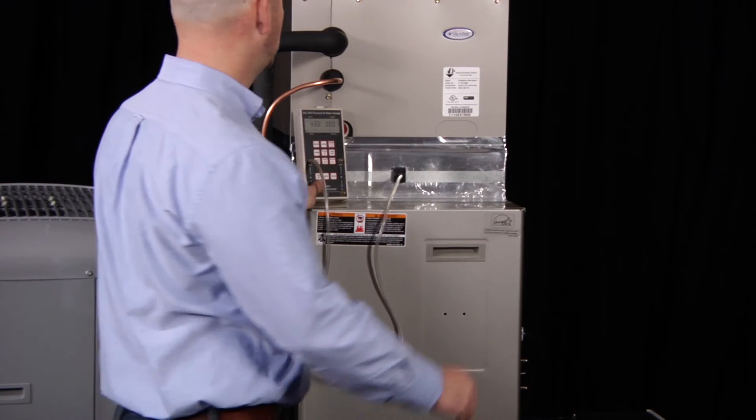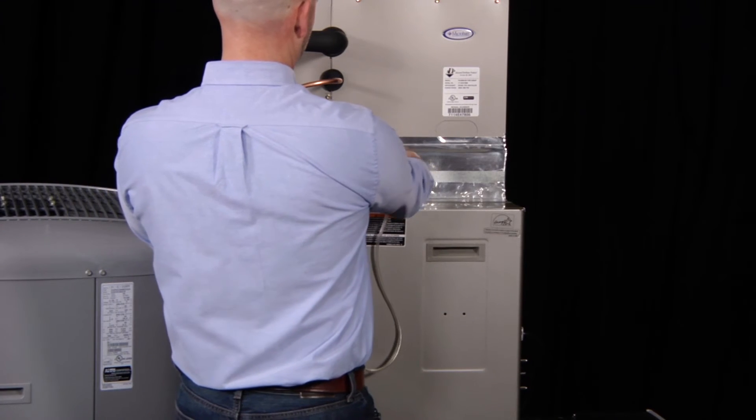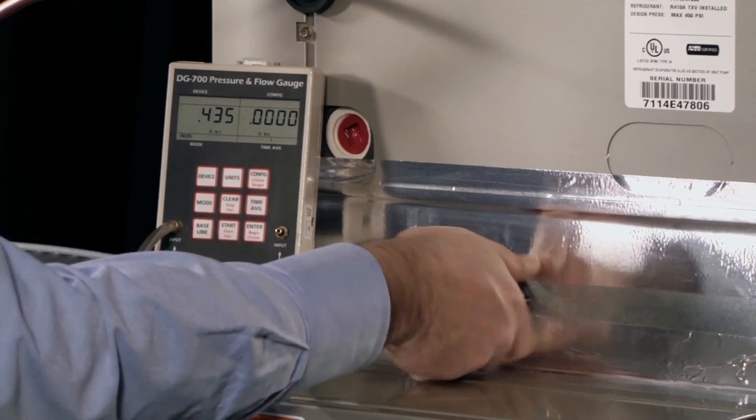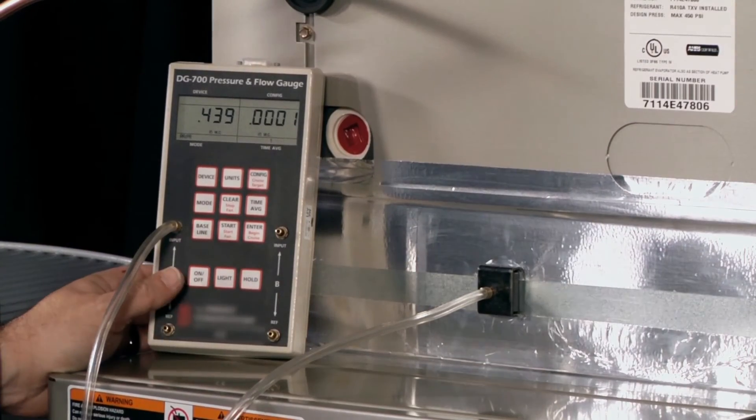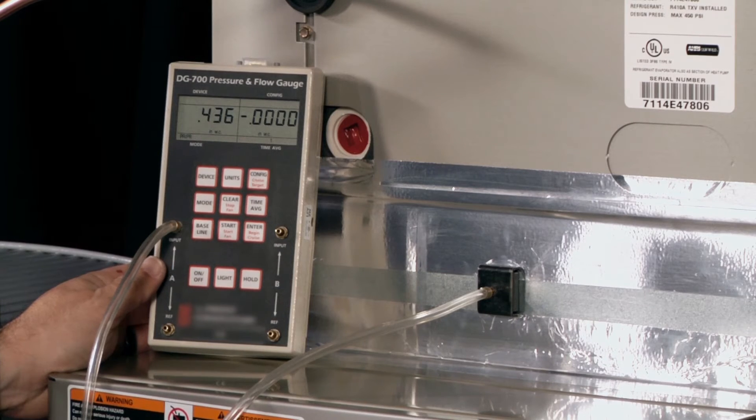Now, what happens if he rotates the static pressure probe 180 degrees so that it's facing the opposite direction? You can see that the static pressure is changing by a little bit, but not very much. In other words, the measurement is not affected very much at all by how the probe is positioned. So that's good news.